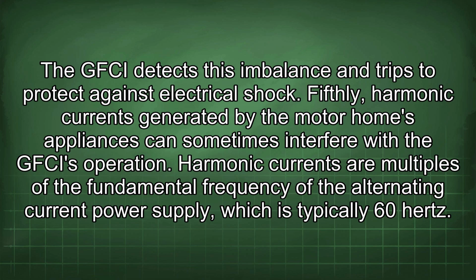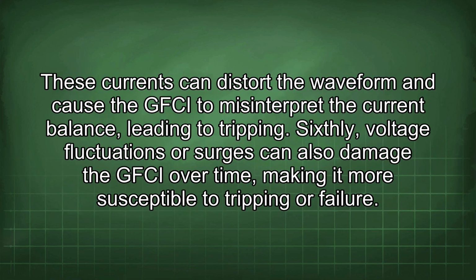Fifthly, harmonic currents generated by the motorhome's appliances can sometimes interfere with the GFCI's operation. Harmonic currents are multiples of the fundamental frequency of the alternating current power supply, which is typically 60 Hz. These currents can distort the waveform and cause the GFCI to misinterpret the current balance, leading to tripping.